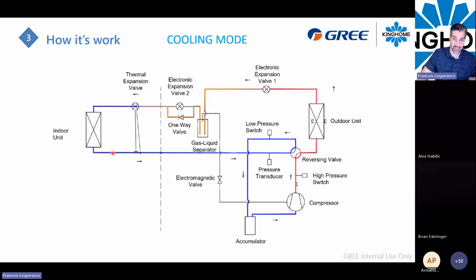So on the other side, you will have your flash gas, so a mix of liquid and gas refrigerant at low pressure. And we will go back to the outdoor unit. We will pass through that four-way valve again, and we will hit the accumulator right here.